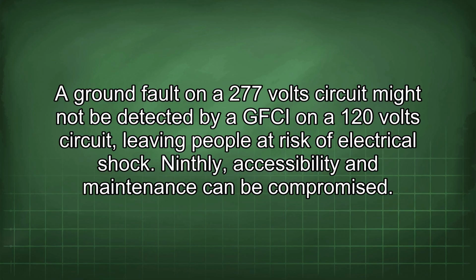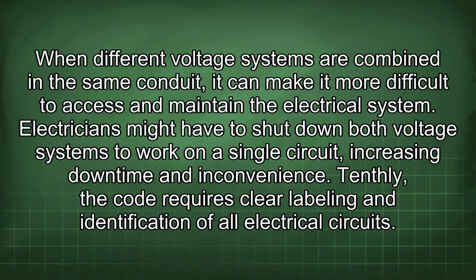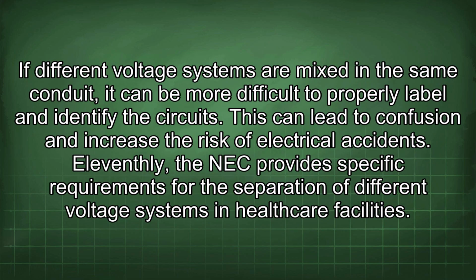Ninthly, accessibility and maintenance can be compromised. When different voltage systems are combined in the same conduit, it can make it more difficult to access and maintain the electrical system. Electricians might have to shut down both voltage systems to work on a single circuit, increasing downtime and inconvenience. Tenthly, the code requires clear labeling and identification of all electrical circuits. If different voltage systems are mixed in the same conduit, it can be more difficult to properly label and identify the circuits. This can lead to confusion and increase the risk of electrical accidents.